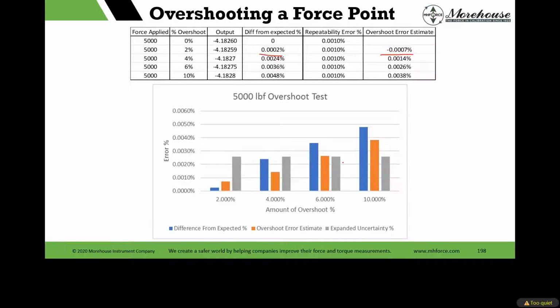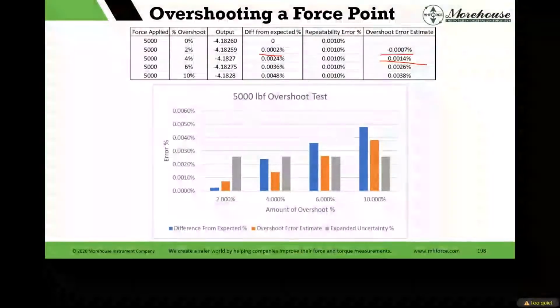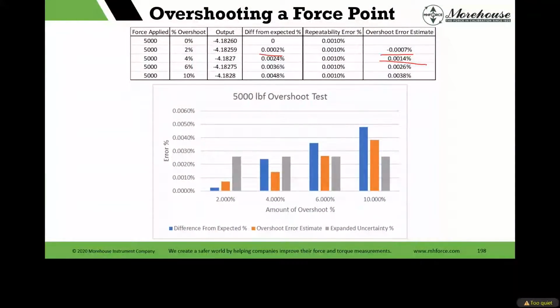As soon as I get to like that 4%, 6%, and 10%, I probably should start my run over, depending on what you think and what you do. At 4%, depending on what I'm calibrating, if I'm calibrating a dynamometer or dynafor, I'm not restarting. I'm not restarting at a 6% overshoot on a device that's reading to 0.1% of full scale. Though at some point, I do want to consider it. If I'm calibrating another customer's load cell, if I'm above 2%, I really should restart my run.